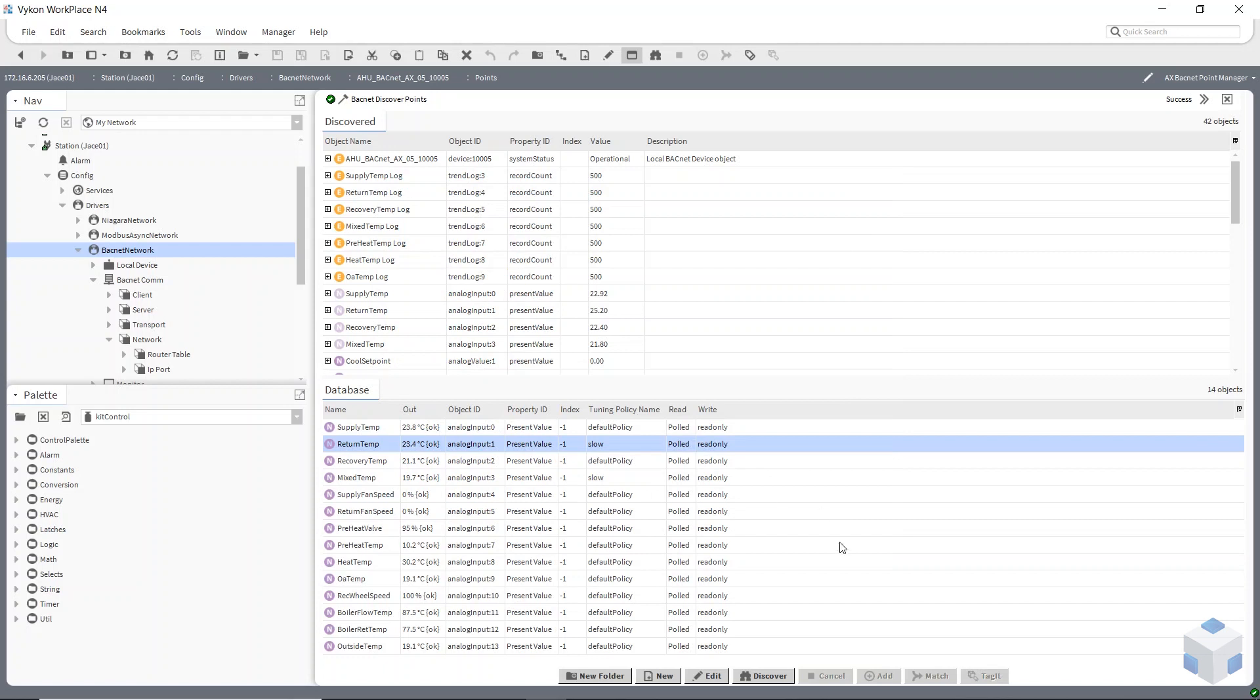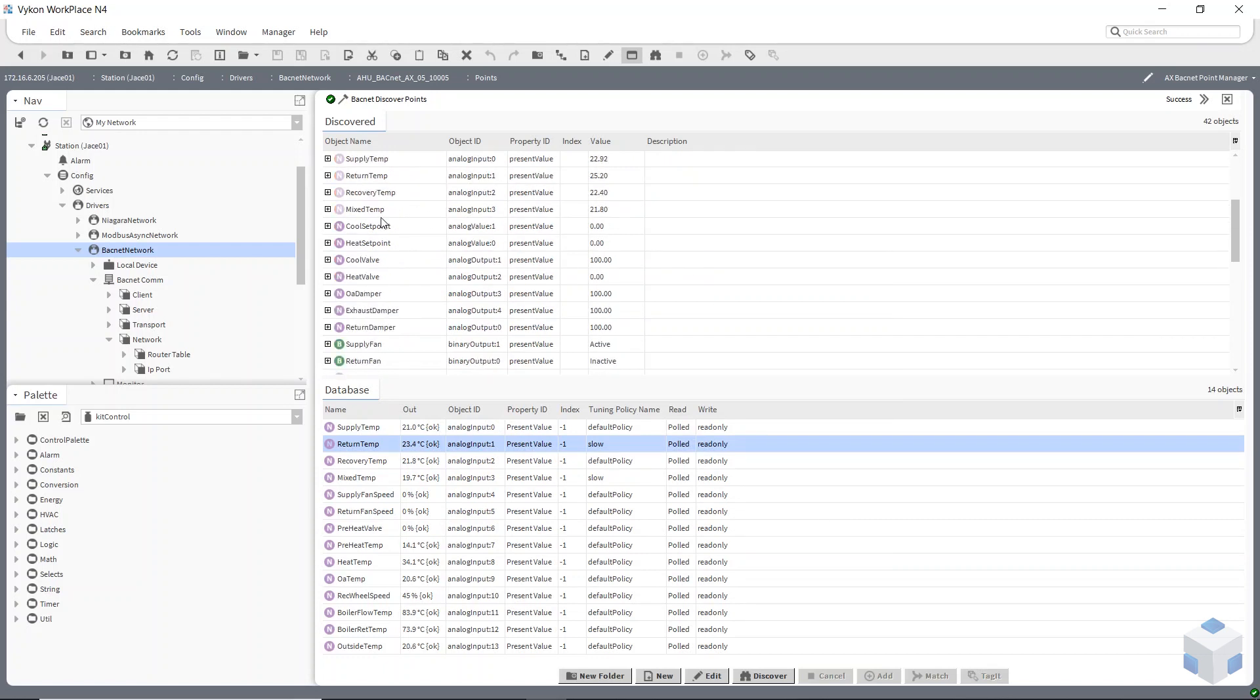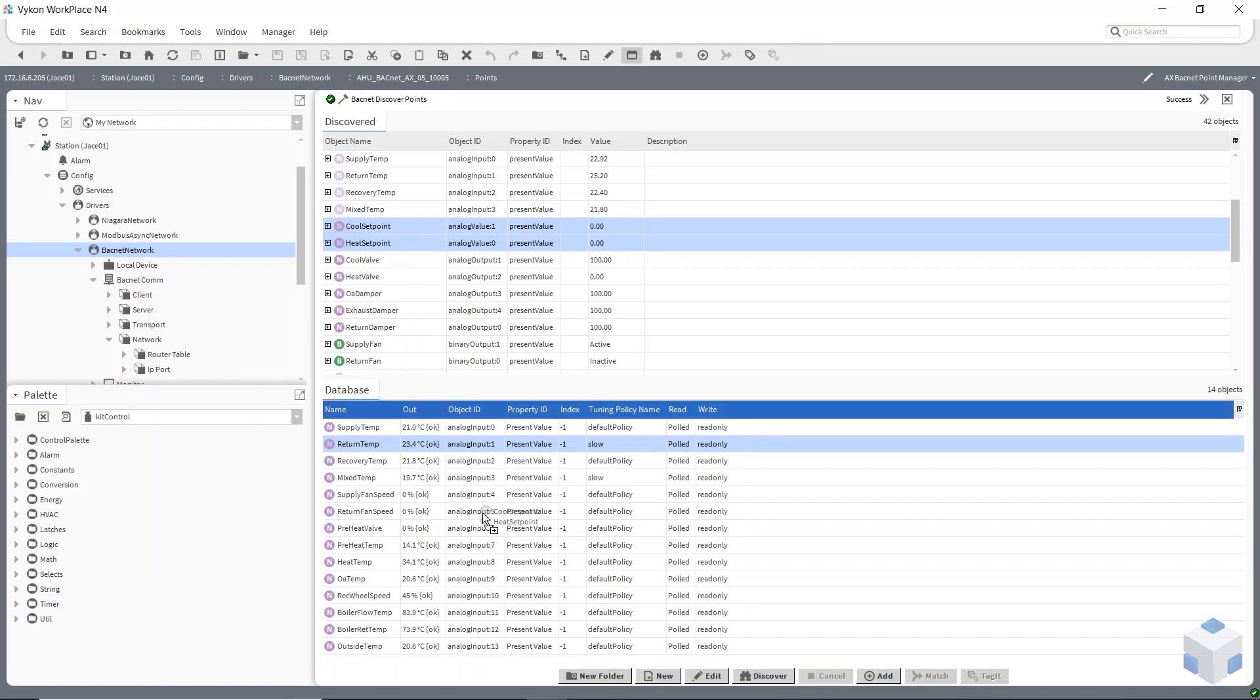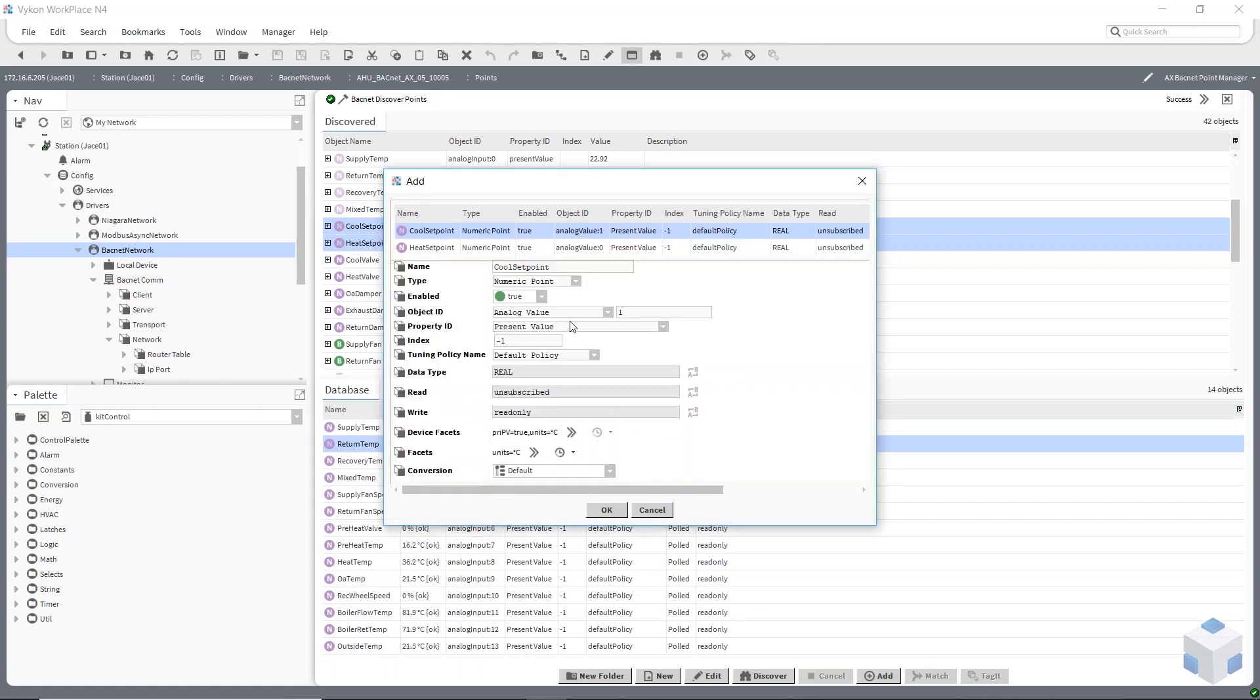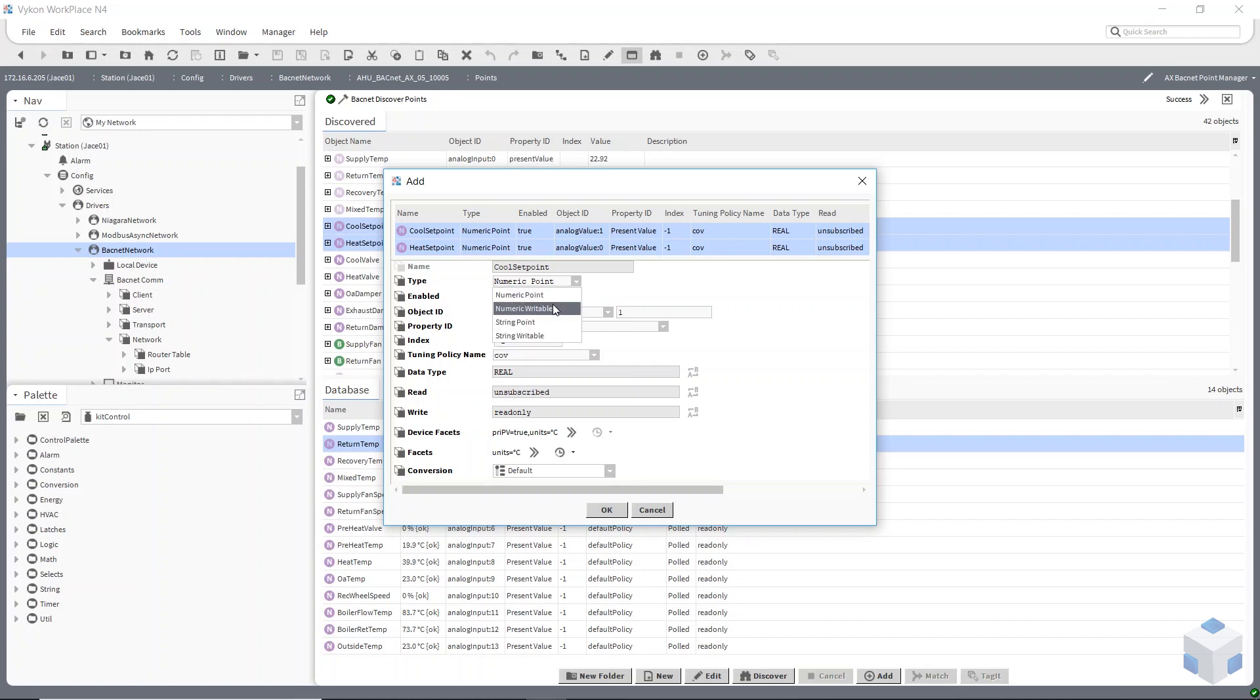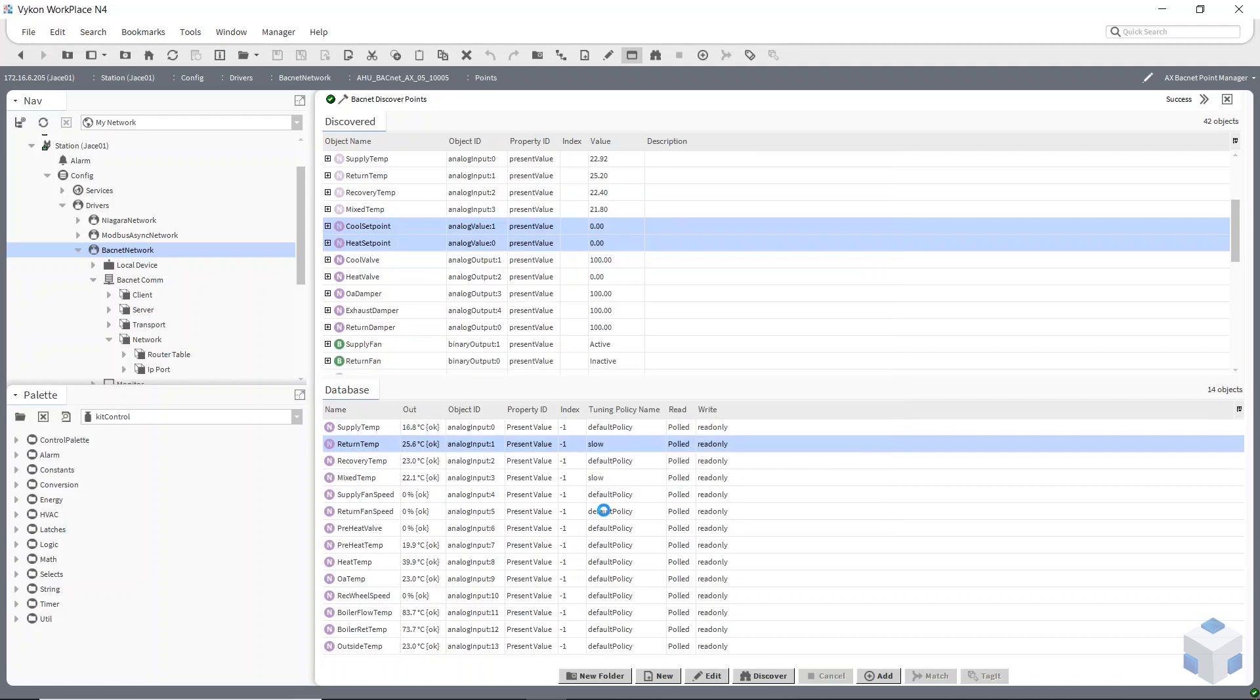So you can just change all these policies afterwards or you can select multiple. Here's my setpoints, here my heat and my cool setpoint. If I add these two at the same time just by dragging them down again I can use this multi select wizard to change both of them at the same time. So I can put this on a COV every time it changes value and make sure also that they're writable, these points. And then once you've made something writable it goes back to enabled false so we have to take care of that as well.